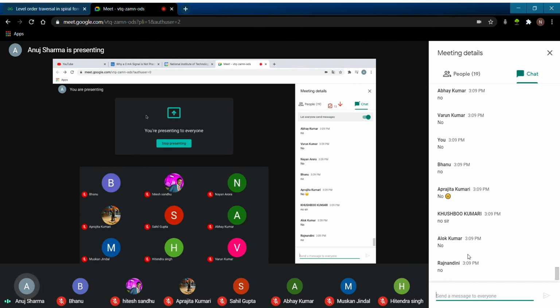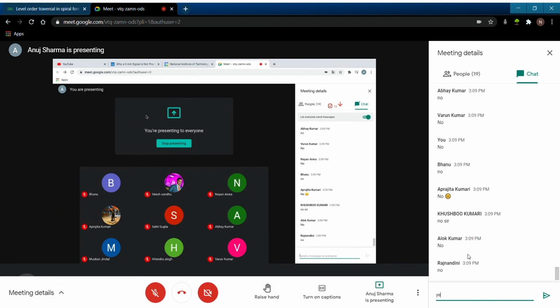Let me repeat it: the question was why his 4 to 20 milliamp output is fluctuating when he is changing his process observation from 0 to 5 to 0 to 0.1. The answer was that when you change the range of your observation, the process fluctuations are added into your signal, and since the fluctuation is relatively more, you get more fluctuations in the respective signal. So you need to change, alter, tune, or calibrate it according to the range also. Did you get it now, or should I repeat it again?